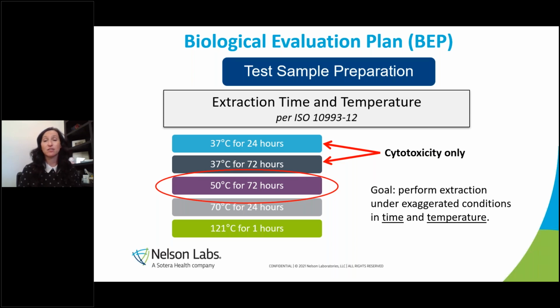test, the preference is to use 50 degrees for 72 hours. And when I say every other test, I mean mostly outside of hemocompatibility, because they have their own special extraction conditions that we comply to. So remember that when you extract, the goal is to perform an exaggerated extraction in time and temperature. So keep that in mind. And I would say, if you say, oh, my device is only used at body temperature and only used for a day, always start with 50 degrees, even if you're nervous that you'll have issues, because FDA and regulatory agencies will want to see data for why you have to use lower than 50 degrees for everything outside of cytotoxicity.